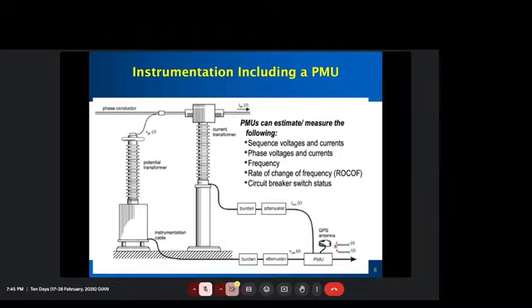And then what do we get? We get the phasor, and you have to feed it with the GPS. It also gives you sequence voltage and current, phase voltage and current. It gives you frequency, and it can also tell you rate of change of frequency, because you got the frequency at time t, and then after a few milliseconds you also got the new frequency measurement, so it can give you rate of change of frequency.